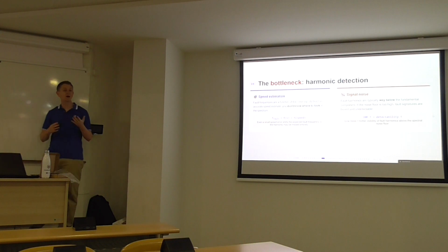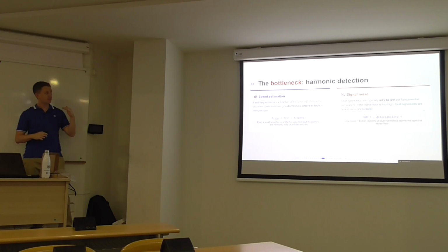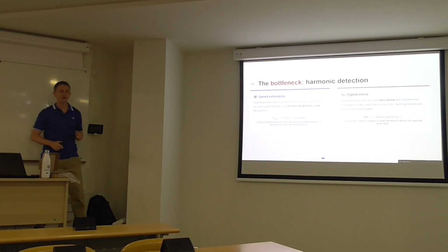And the other one is the signal noise. Fault harmonics are usually way below the fundamental component in terms of amplitude. The fundamental component has a very high amplitude and the fault harmonics are very low. So if the noise floor is too high, it will bury these signatures and the harmonics will become undetectable. So the higher the signal to noise ratio, the better the detectability. Just to keep in mind, low noise means better visibility of all harmonics. That's a key takeaway: low noise, better visibility, and that's what we want.